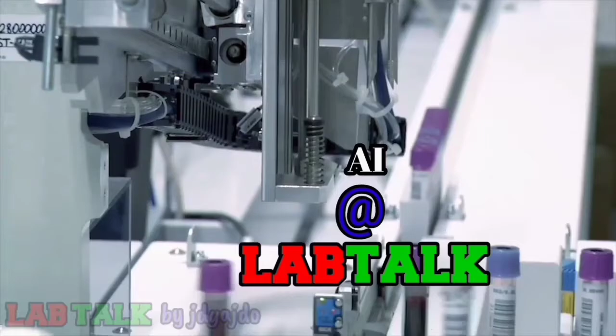LabTalk. So the next thing in equipment qualification is design qualification or user requirement specification. Now design qualification should actually be discussed before the installation qualification, because here we have to decide what type of equipment we have to purchase and what the features or technical specification of the equipment should be. But as this is not a mandatory requirement from any accreditation body or any of the standards, we are discussing it after the IQ, OQ and PQ.